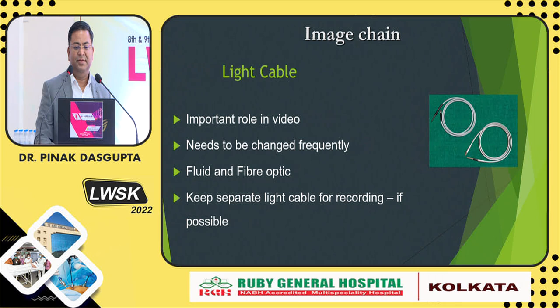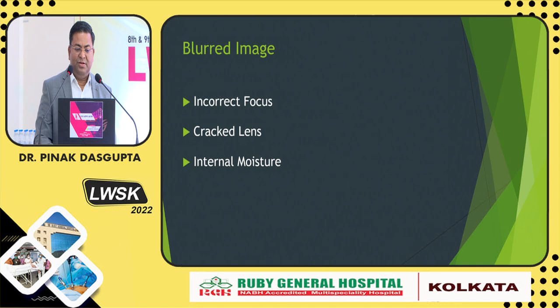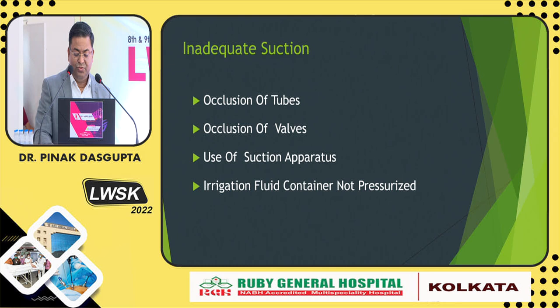Again, blurred vision could be because of a cracked lens, or sometimes because the OT is kept chilled, maintaining a temperature of around 18 to 20 degrees. This sometimes produces moisture between the camera processing head and the telescope. One has to check for this moisture, which also decreases vision. It can also be due to inaccurate focusing.